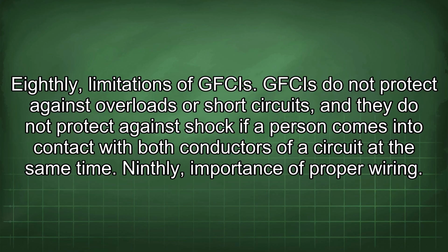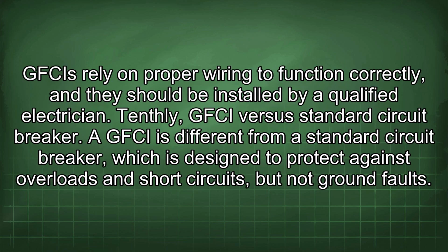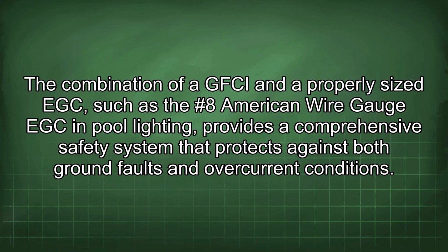Ninthly, importance of proper wiring. GFCIs rely on proper wiring to function correctly, and they should be installed by a qualified electrician. Tenthly, GFCI versus standard circuit breaker. A GFCI is different from a standard circuit breaker, which is designed to protect against overloads and short circuits, but not ground faults. The combination of a GFCI and a properly sized EGC, such as the #8 American wire gauge EGC in pool lighting, provides a comprehensive safety system that protects against both ground faults and overcurrent conditions.